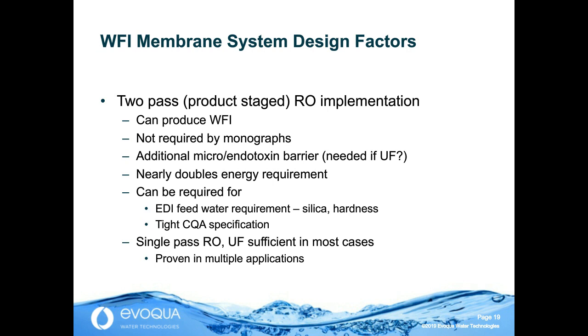Now, there could be a process need as opposed to regulatory for two-pass. The electrodeionization units that are going to be used in most of these systems have feed water requirements: relatively low silica, hardness, certain metals. So on some feed waters, two-pass RO could be needed for the electrodeionization spec, or if there's a very tight critical quality attribute, low total organic carbon, very low conductivity, then a second pass of RO could be logical.